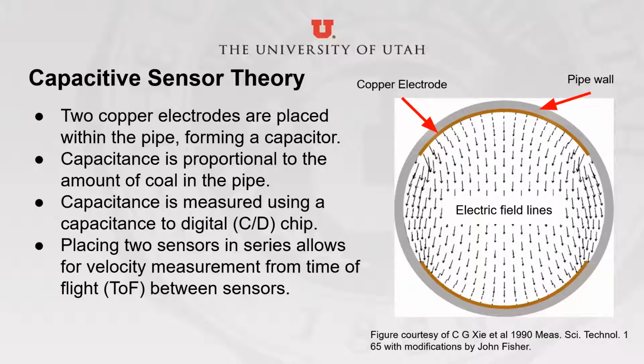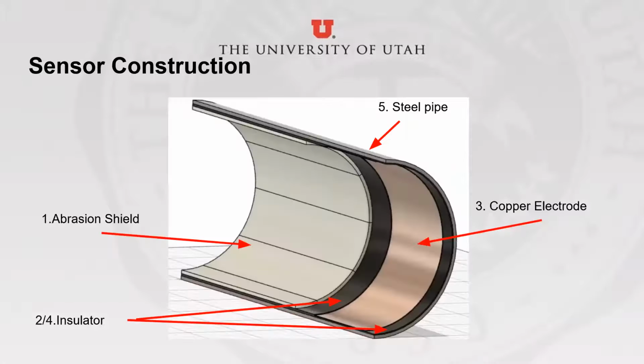So by placing 2 of these sensors in series along the pipe, we can track artifacts in the flow between the 2 sensors and estimate the flow velocity. This here is how a sensor would be constructed. From the inside out, you would need an abrasion shield, an insulator, the actual electrodes, another insulator, and then the pipe.